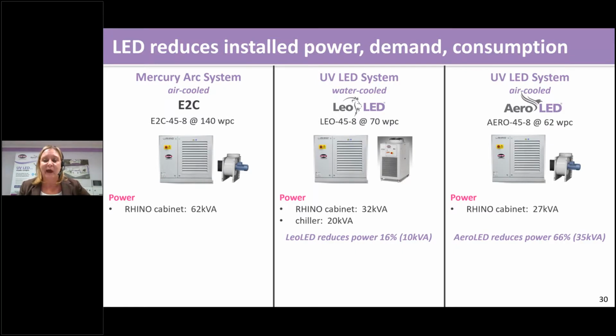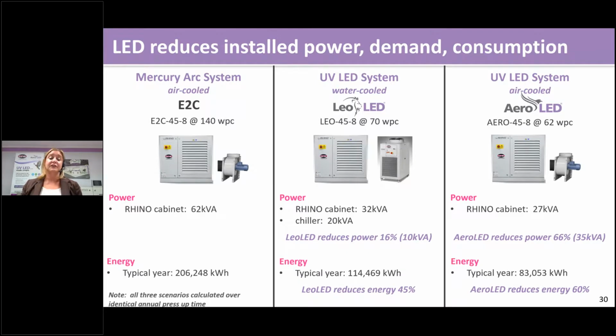Lowering that apparent power from 62 to 32 to 27 is sustainable. This does more for you than buying renewable credits from solar and wind on the line, because this is something you control in your own plant. And it reduces your power in the example on the far right by as much as 66%. And so that translates into energy, right? Power over time is energy. So in a typical year, you're going to pull kilowatt hours as shown on the screen. Going LED reduces your consumption over time.